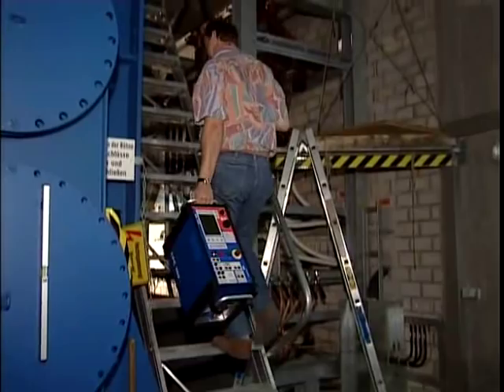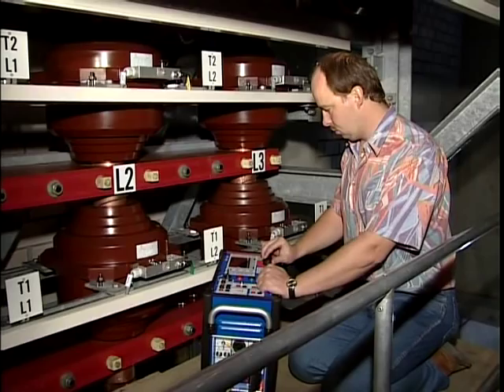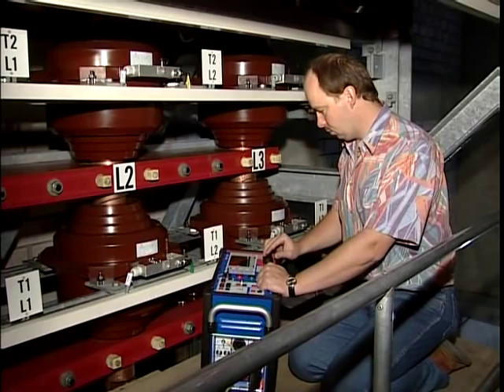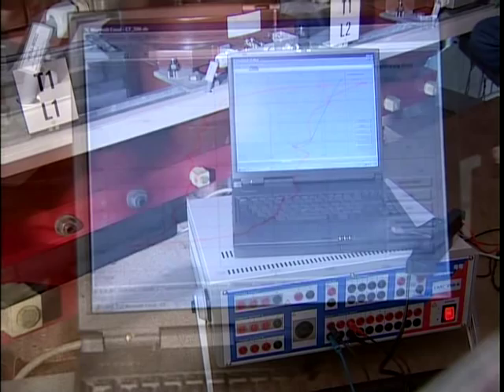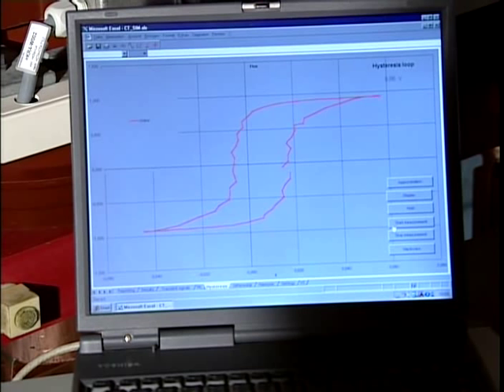The CPC100 contains a wide range of functions, such as measuring the CT and VT ratios, winding resistance, burden, magnetizing characteristic, and contact resistance. All of this heavy-duty functionality is in a relatively lightweight package. Note that the CT must not be short-circuited on the primary side while these tests are carried out. With the relay test set CMC256 and specifically developed software using the CM engine interface, the hysteresis loop is oscillated online.